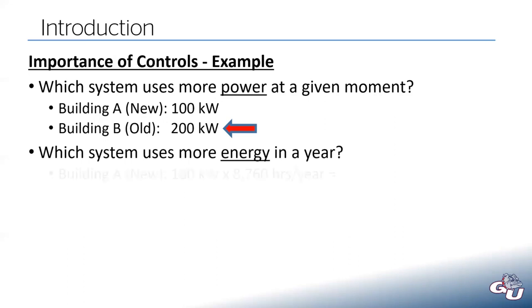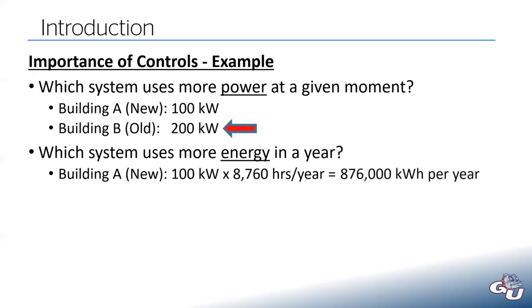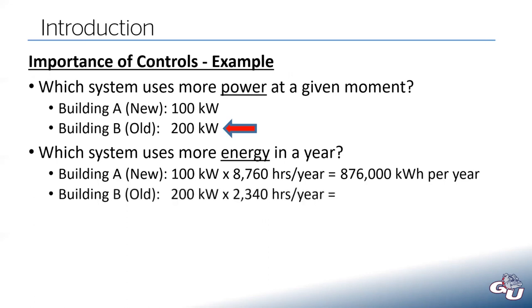And so if you do the math, to arrive at what's called kilowatt hours, kWh, you take your power, kW, and you multiply by your operating hours per year. So 100 kW times 8,760 hours per year, we arrive at 876,000 kilowatt hours per year. So that's how much energy that building is going to use. The old building uses a lot more power, but a lot fewer operating hours. The total energy there is about 468,000 kilowatt hours per year.